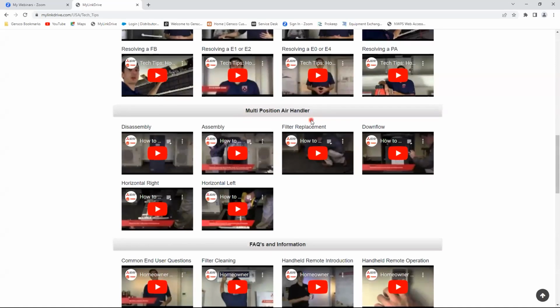Multi-position air handler. This walks you through reconfiguring the unit from a right hand or upflow to a downflow or left hand horizontal. If you are reconfiguring our SVZ, MVZ, PVFY to a left hand horizontal, please be aware that Mitsubishi runs the thermistor wire connecting cable that goes to the thermistors on the coil in the left-hand side panel, and they run it over the lip, which is metal, and these are very thin wires.